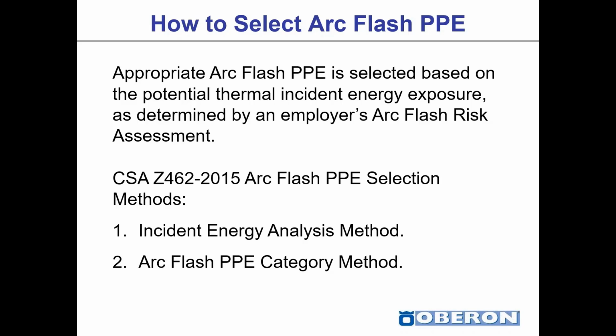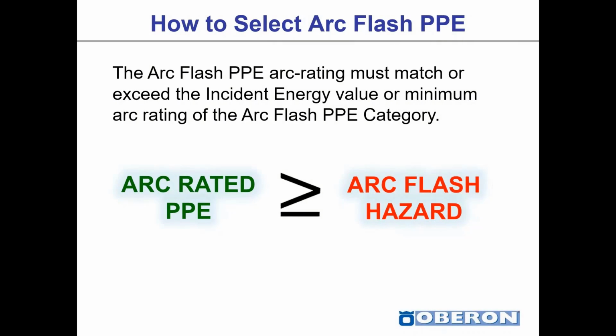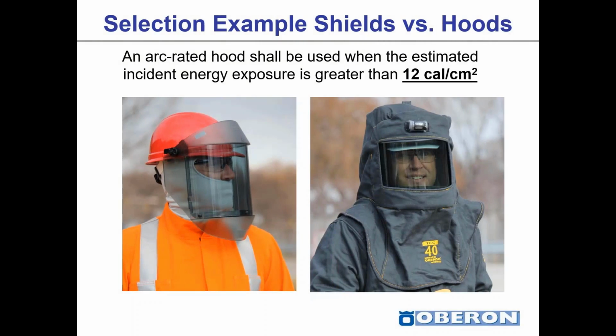And how to select arc flash PPE? Appropriate arc flash PPE is selected based on the potential thermal incident energy exposure as determined by an employer's arc flash risk assessment. So we look at two different methods. The incident energy analysis method, where we look to EasyPower for performing the engineering calculations. Alternatively, we could use the arc flash PPE category method. And selecting your PPE, make sure that the arc rating, so the performance, what we expect from the product itself, is equal to or greater than the arc flash hazard. And then selection examples, we have here an example between a face shield or a suit hood. An arc rated hood shall be used when the estimated incident energy exposure is greater than 12 calories.